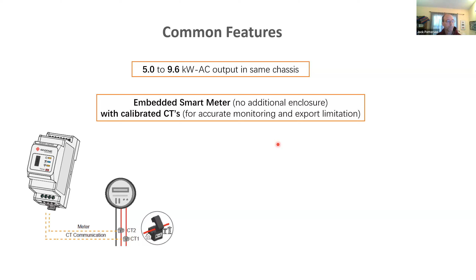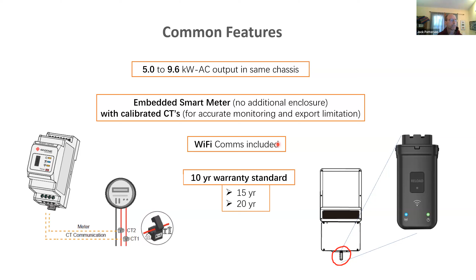Inside the box is also what we call our Wi-Fi dongle. It's a communication device plugged in after you've done everything else, all the conduit and wiring. You plug this in, and this is the device that's going to communicate to the homeowner's router to send data out to our free monitoring site called SEMS. So you'll commission the inverter by connecting to this device, set up the inverter to be the right grid setting, and then you'll also tell the inverter how to talk to the homeowner's router so it can call home and you can go use the SEMS platform. We'll talk more about that platform. There's a standard 10-year warranty, expandable to 15 or 20 years.